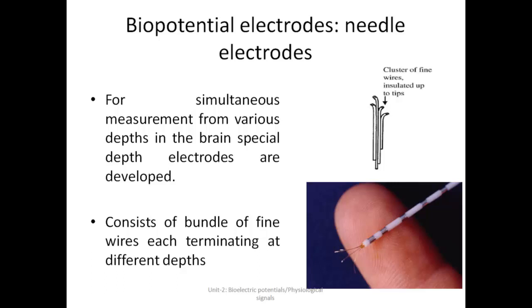Okay. The needle electrodes for EMG consist of fine insulated wires such that their bare tips are in contact with the nerve, muscle or other tissues from which the measurement is to be made. The remaining portion of the wire is covered with some form of insulation to prevent shorting. The wire electrodes of copper and platinum are often used for EMG pickup from specific muscles. The wires are either surgically implanted or introduced by means of a hypodermic needle that is later withdrawn, leaving the wire electrode in its place.